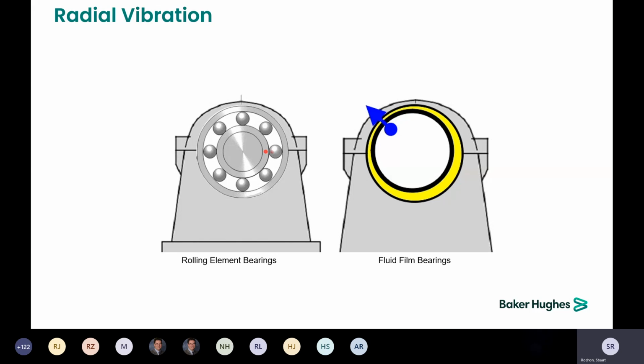Quite often you see that with nuclear steam turbines. They will have a velometer mounted in the same plane as the proximity probe. And so with that, we can get the motion of the shaft relative to the mounting point, and the motion of the machine case relative to a point in free space. And by summing the two, we can get the motion of the shaft relative to a point in free space. So you can get a lot more information.